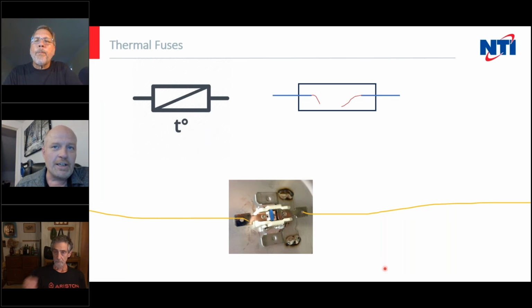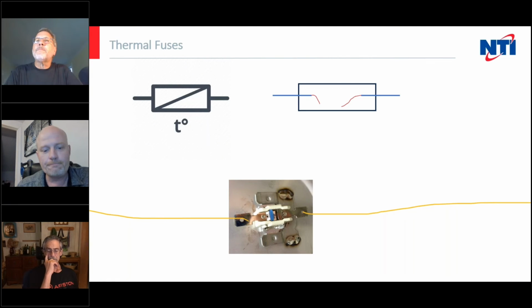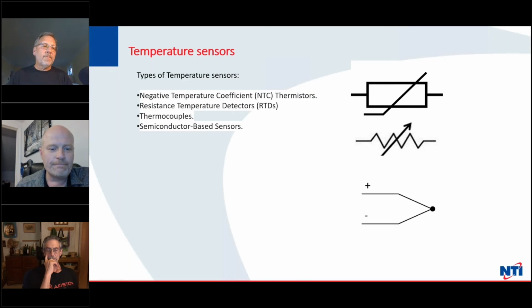So shown in the picture here is the thermal fuse that's on the back of a LX 300 up through 800. Again, if these trip, it's a very serious indication. Something's probably gone pretty badly wrong for these to trip, because they trip at like 350 degrees. Oh, my notes. Yeah, you've got to get them really hot. That's like that TI burner, the top of the door you said burned up. It had to get pretty hot. Yeah, we added a snap disc. We didn't put a thermal fuse on, but we added a snap disc to those.